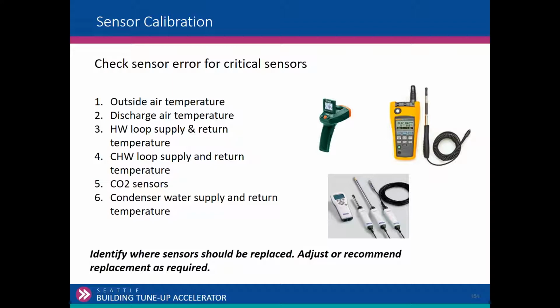Critical sensors, we talked about outside air temperature. That's fairly easy. Does it make sense? Is what's showing on the BAS, if you're controlling based on that, what my smartphone says? Discharge air temperature, we can measure that. We can insert a measuring instrument into that. We can trend it and see if the sensor and our measurement makes sense. Hot water loop supply and return temperatures. If you don't have a building automation system, I have contact sensors that you can either adhere to or just use a hose clamp and strap and then put insulation over it so that we can log hot water supply and chilled water temperatures. So we've got various tools out there that we can use to verify whether or not these reset strategies are in place.